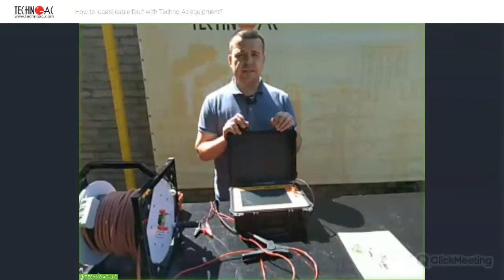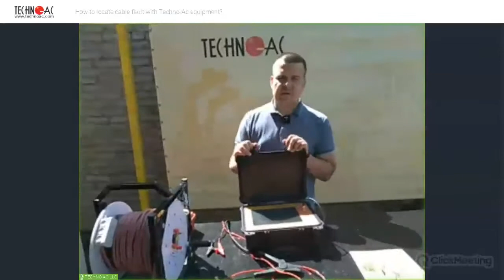What's time domain reflectometry in general? You know that the cable fault location market has two kinds of TDR devices to offer. The first one is OTDR, the time domain reflectometer for optic fiber cables. Unfortunately, TECHNO-AC doesn't supply this equipment. That is why we're switching to the other type of TDR equipment, which is TDR for copper cables, power cables, and network cables. In this case, our equipment suits best for the location of twisted pairs, coax cables, and power cables. This particular device is the most powerful, but the principle behind it works for every model of TECHNO-AC TDR.